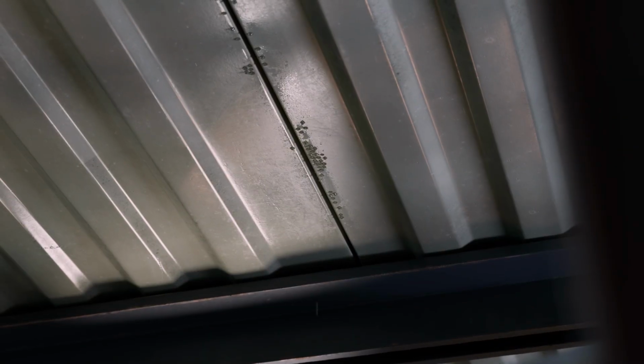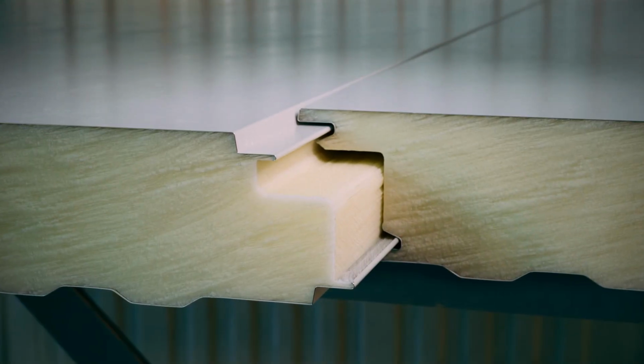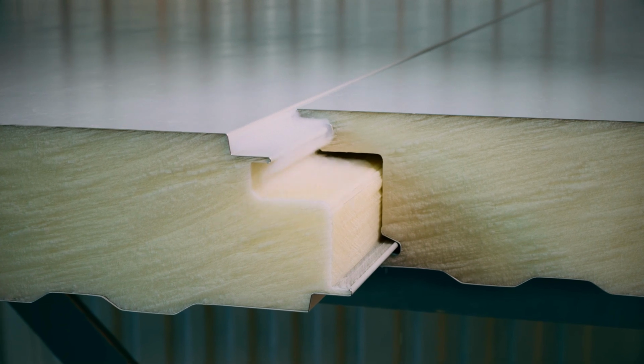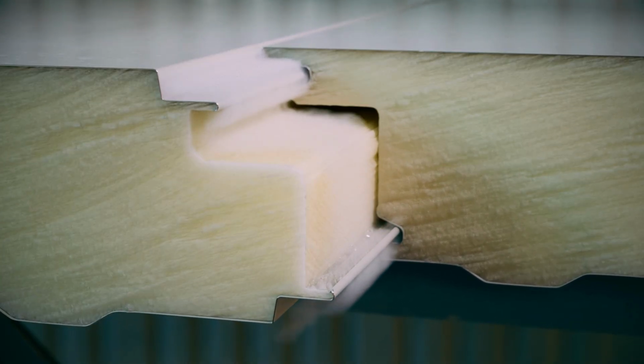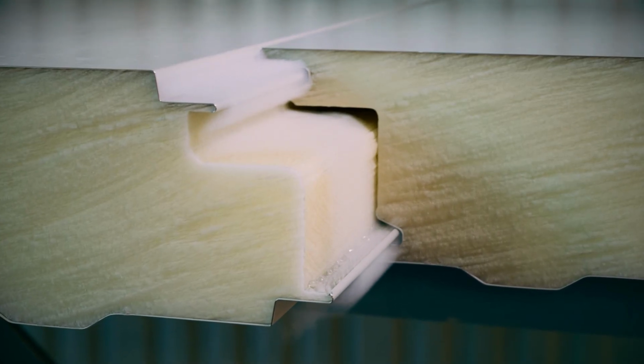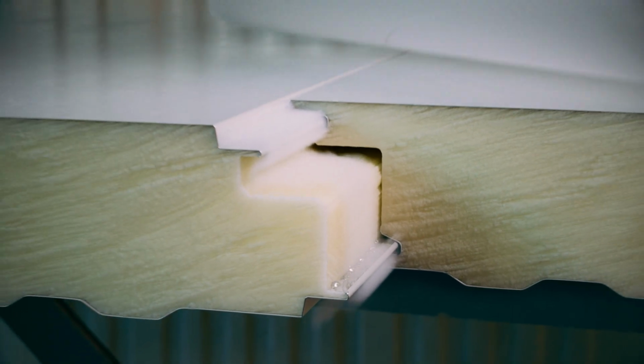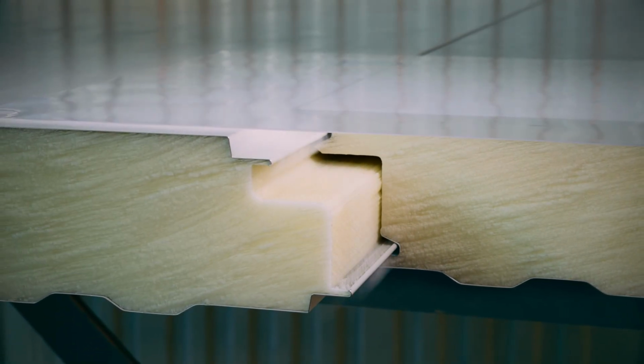A problem with a room's vapor barrier exists when condensation occurs through pinhole-size openings in a room's walls and ceilings. If a hole exists in a vapor barrier, any vapor pressure difference between the inside and the outside forces vapor through the hole. To fix this, the holes must be sealed on the warm side with a true vapor barrier product.